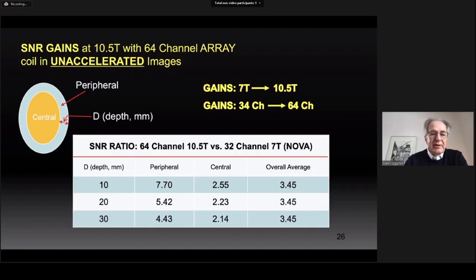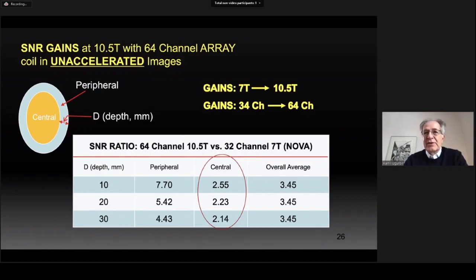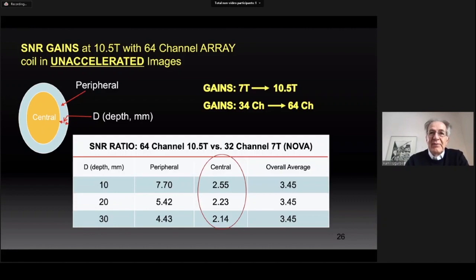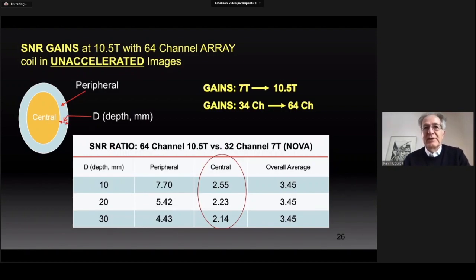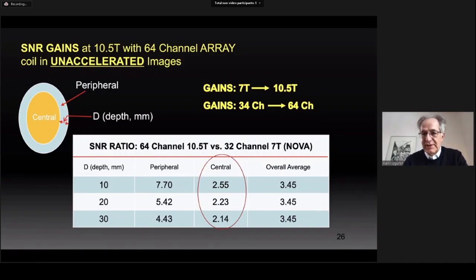The data is presented with the image volume segmented into peripheral and central regions, with a boundary whose distance from the periphery is indicated by the parameter d. In the central volume there is approximately a two-fold SNR gain at 10.5 tesla versus 7 tesla, varying about 20 percent as d is increased. This agrees with expectations: approximately 32 channels captures all of the available intrinsic SNR in the center of human-head-sized objects; channel counts beyond that do not lead to further central SNR increases, but higher magnetic field strengths lead to super-linear gains in the center — in this case an expected factor of approximately two.